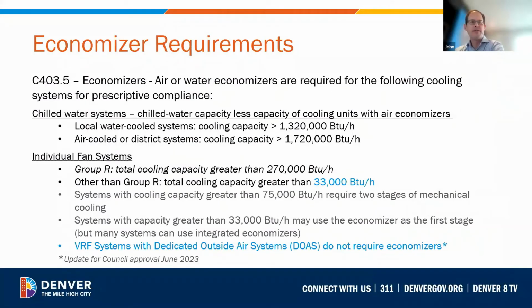One other note, in blue on this slide, is that there is a pending clarification that VRF systems, the variable refrigerant flow systems that use dedicated outside air systems for ventilation, do not require economizers. You can look for that update in June of 2023.